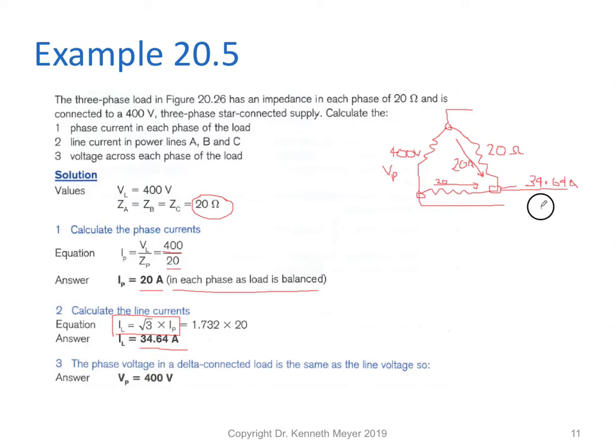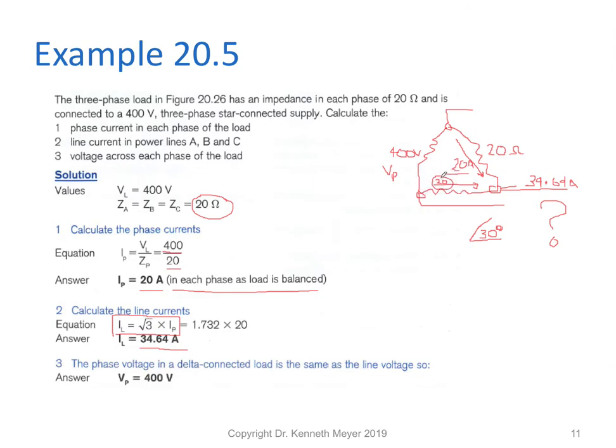Why is the line current not simply 20 plus 20 equals 40 amps? It's because there is a 30 degree angle between the two currents, therefore we end up with 34.64 amps and we have to use the formula I_line equals square root of 3 multiplied by I_p.